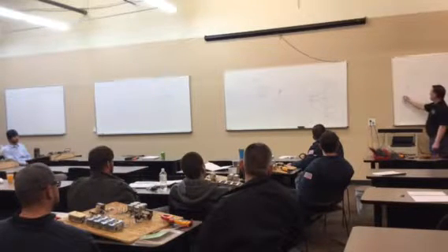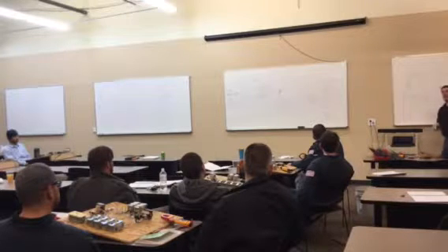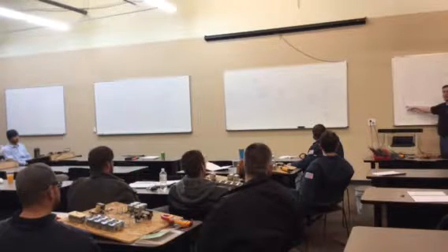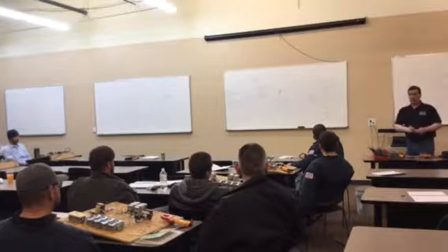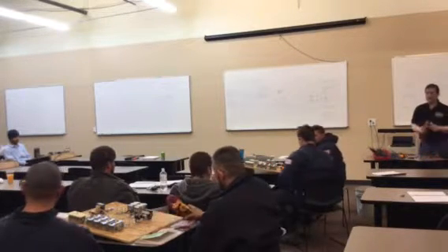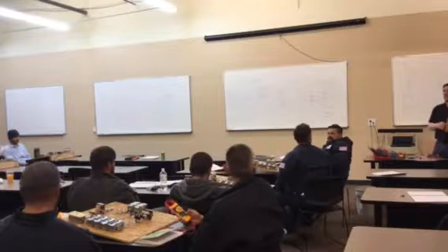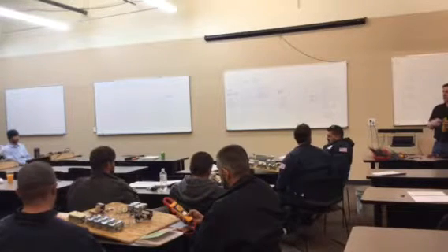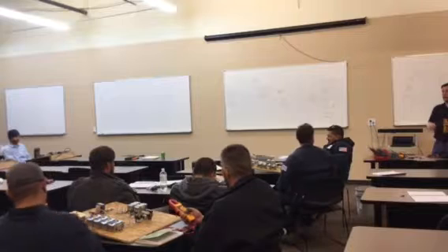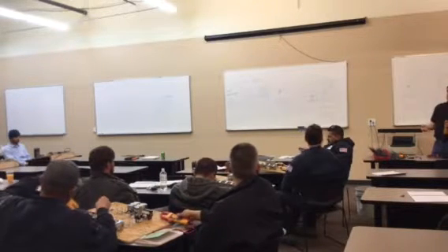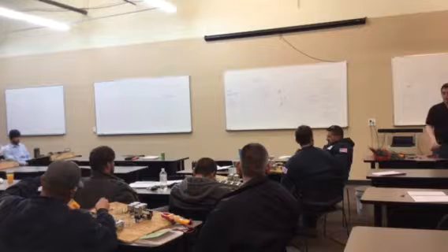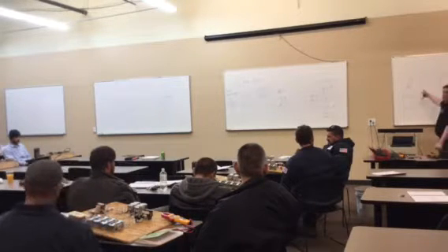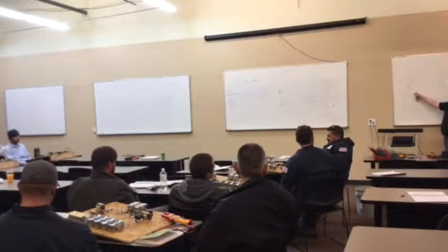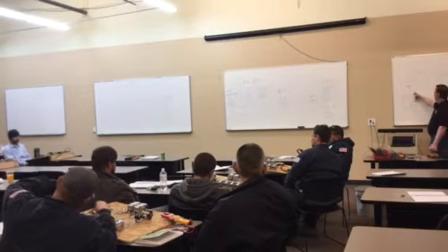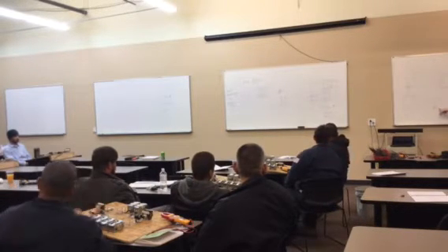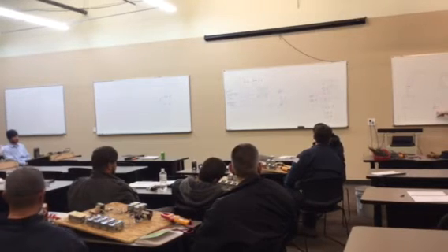So my first meter is measuring transformer output voltage, and I want this set to record. If you've got a min-max feature, your meter is constantly looking at what it's seeing, and as soon as it sees a deviation, it will record it. It will record the highest value it sees and the lowest value it sees, and lock it into a hold screen. So once you're measuring voltage, you put this on automatic hold mode or min-max mode, whichever one you have. Then you have this other one set up to just measure voltage. You're watching this meter...